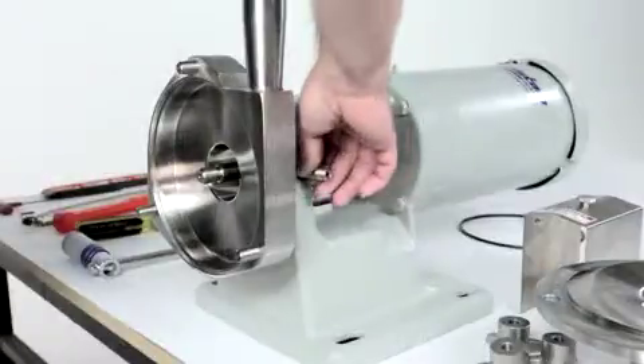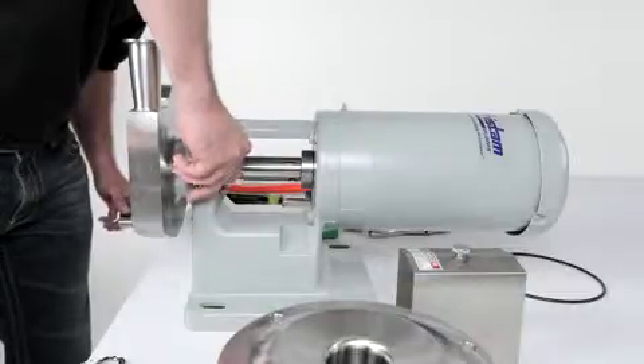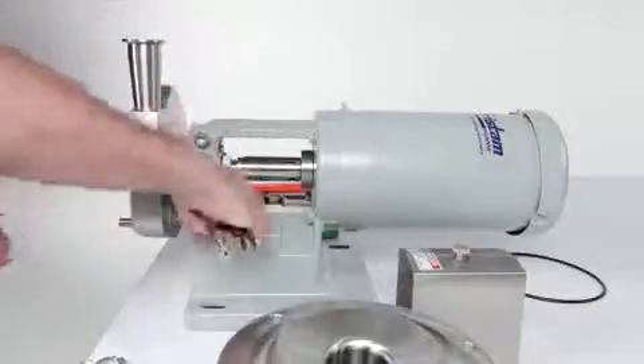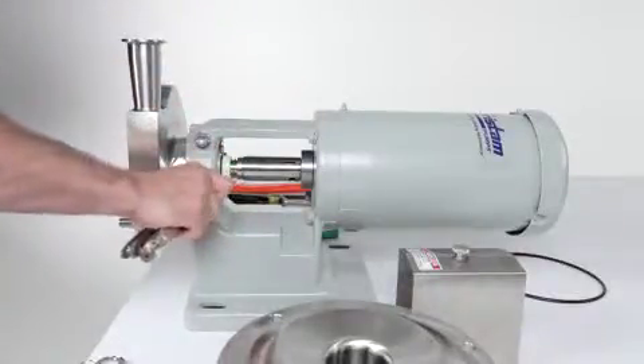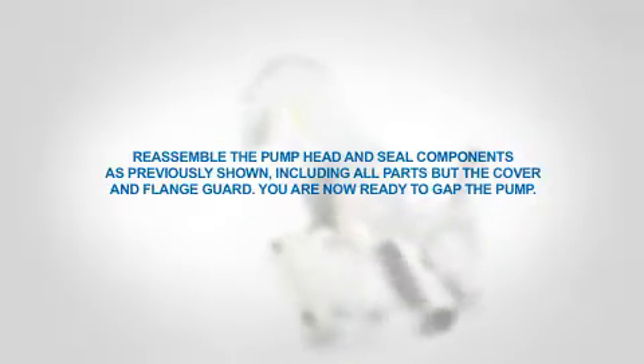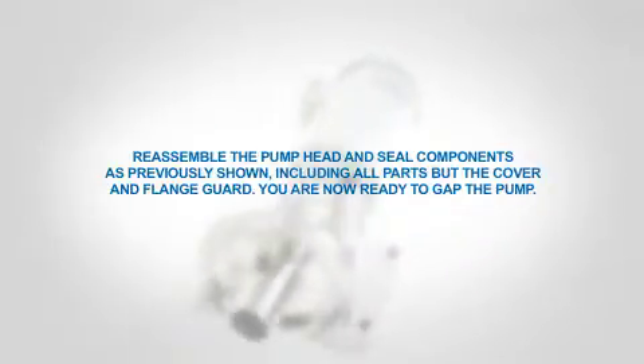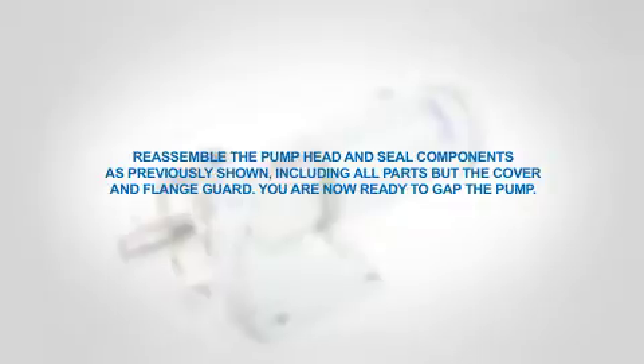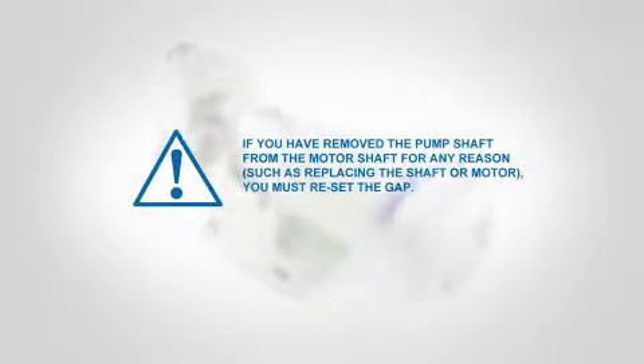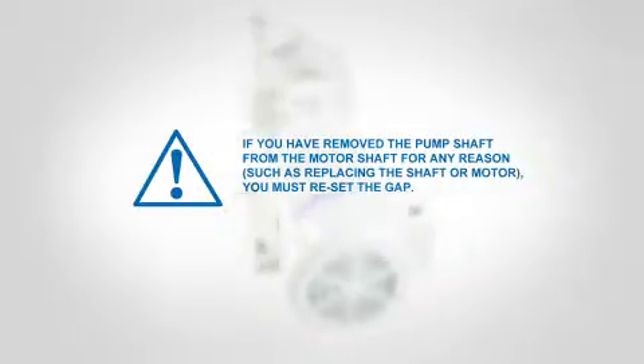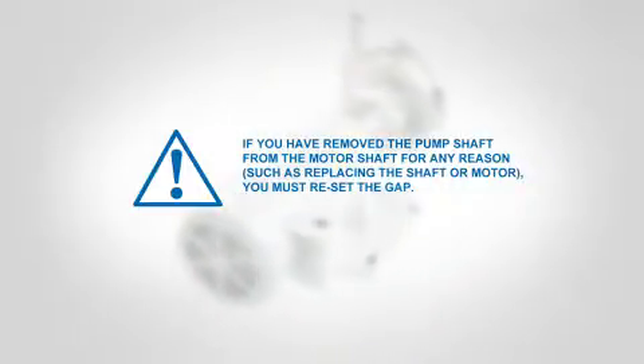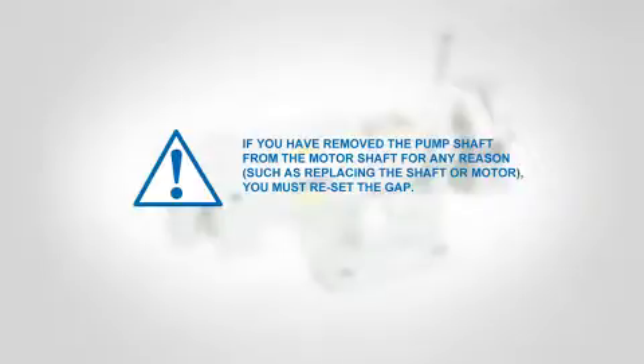Install the seal water pipes for double mechanical seals or water cascade option by threading them into the housing and tighten with the pliers. Reassemble the pump head as previously shown, including all parts but the cover and flange guard. You are now ready to set the impeller gap. If you have removed the pump shaft from the motor shaft for any reason, such as replacing the shaft or motor, you must reset the gap.